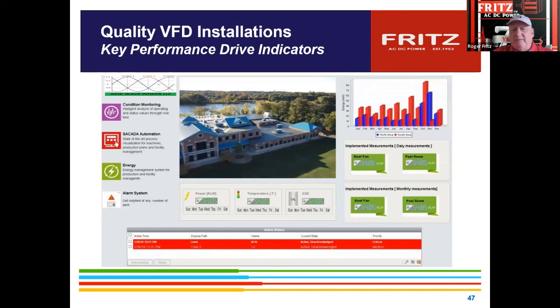This happened to be on a facility up in the Lowell area where you can see here, this was the loading factor of everything prior. And by the time we put in the BMS and drive controls, we end up seeing about a 45% reduction in their total power bill.